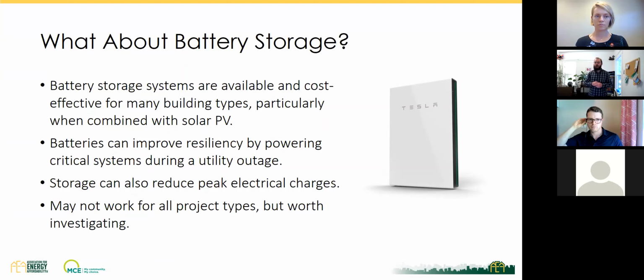They pair really well with solar PV systems. They can also reduce peak electrical charges by load shifting. So on larger properties with demand charges, by shifting our loads we're able to smooth and flatten our demand curve, and that can result in considerable cost savings. They definitely don't work for all project types, but it's worth considering and looking into, and there typically are considerable incentives available to help buy down the cost.